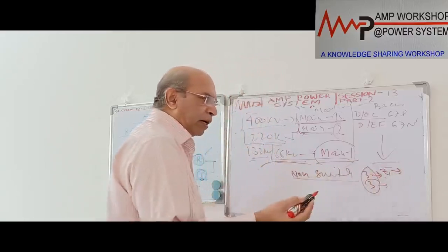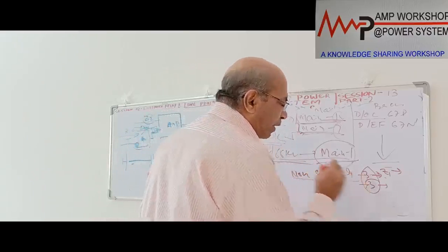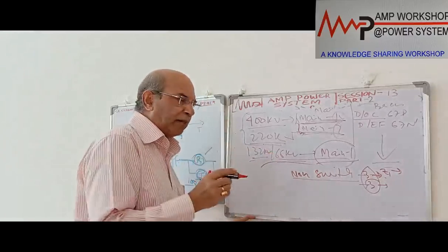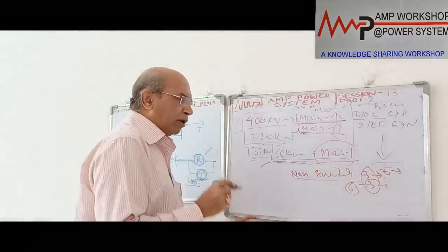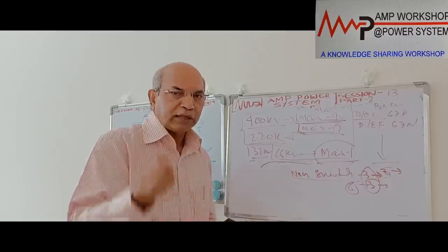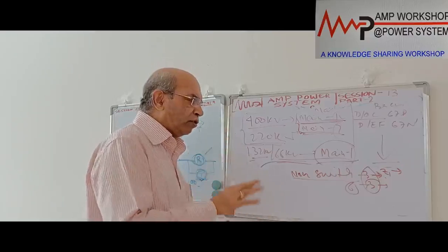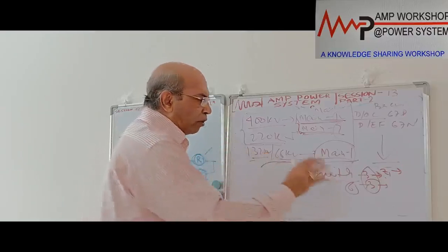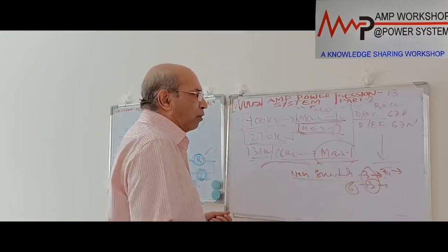Zone 3 has one measuring and one starter for the phase fault. Similarly for earth fault. So each element is an independent relay, an independent element inside the same relay. All these things, so 6 elements will be independent of each other. So in the case of a non-switched scheme, any zone element cannot be switched to another zone element or other fault element. So phase fault and earth fault, and for each zone there is an independent element for the non-switched scheme. That is the main difference between the switched scheme and the non-switched scheme.